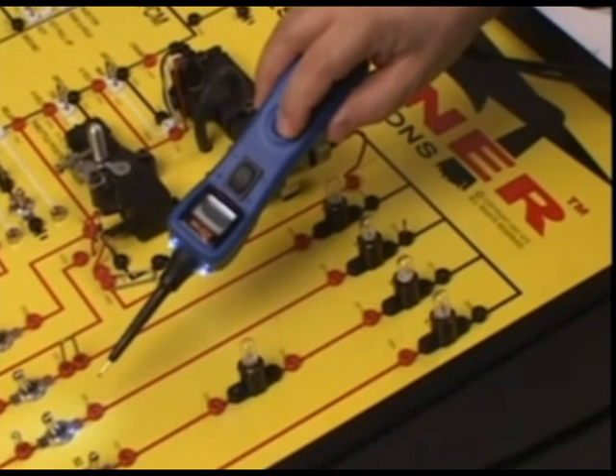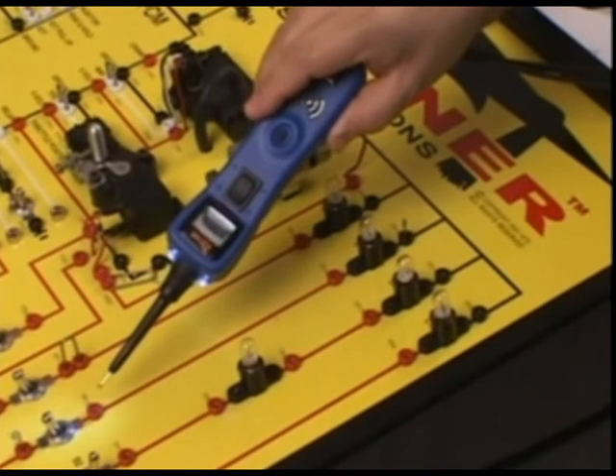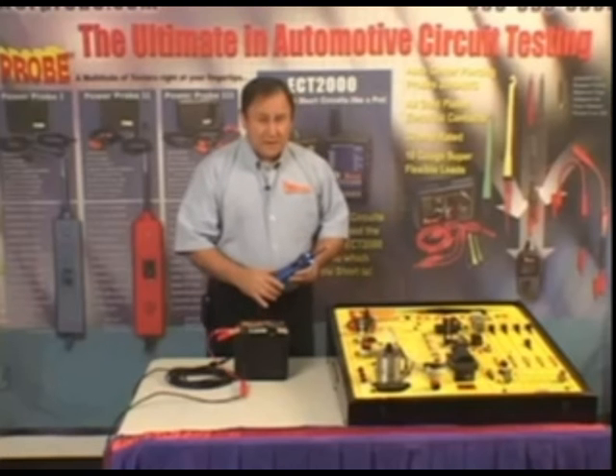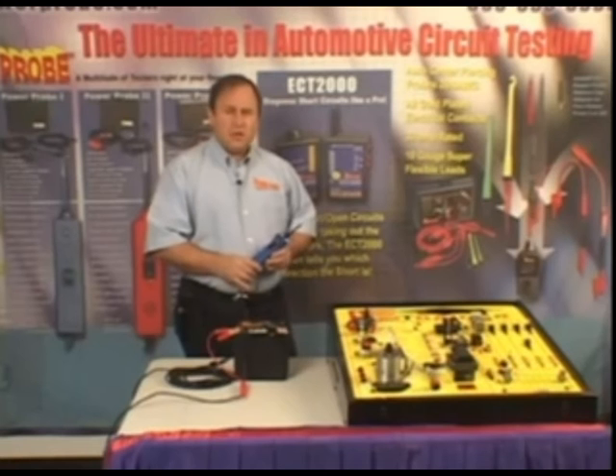The next extended press of the mode button puts it in negative peak. Negative peak mode monitors, captures, and displays the lowest voltage reading during the test.